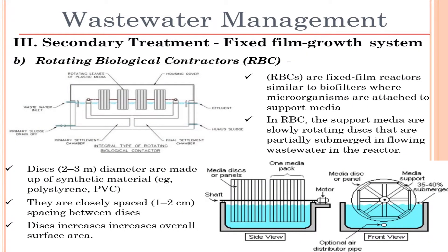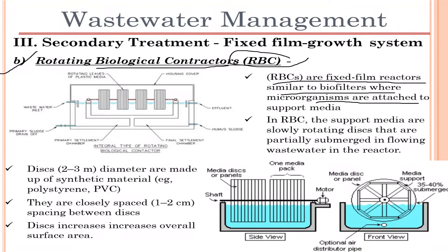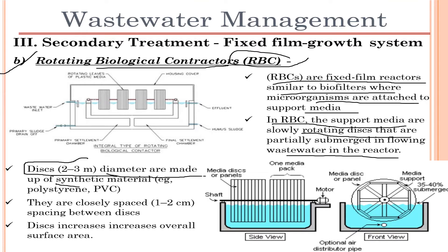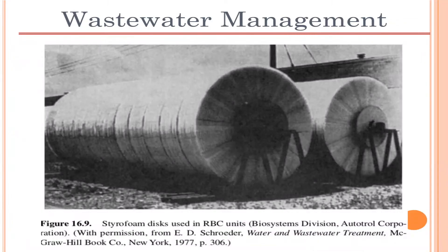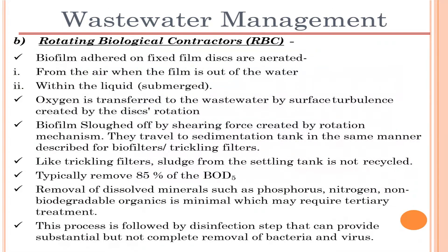The second type of system is Rotating Biological Contactors, or RBCs. RBCs are fixed film reactors similar to biofilters where microorganisms attach to support media. In RBCs, the support media are slowly rotating discs that are partially submerged in flowing wastewater in the reactor. The discs are two to three meters in diameter, made of synthetic material such as polystyrene or PVC, and are closely spaced about one to two centimeters apart. This spacing increases the overall surface area.